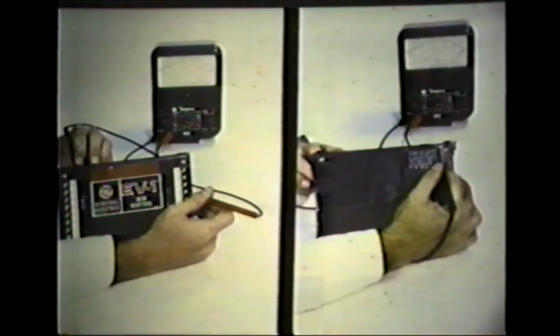Two quick checks can be made to verify if the card is bad. Check for continuity between R4 and terminal 6 on the rear plug. An open in this circuit indicates a bad card. Also, a strong burnt odor in the vicinity of the rear card plug indicates a blown card.